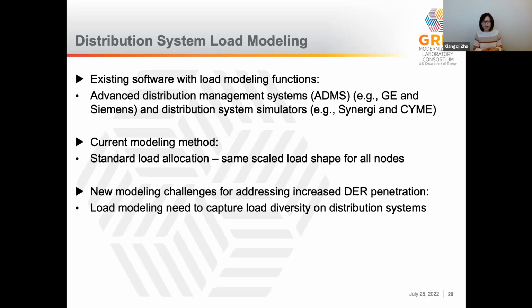One group is the advanced distribution management system, or ADMS, and the other is distribution system simulators like OpenDSS or CYME. Load modeling right now is a basic module in those software packages, often serving as a function called load allocation. When we perform time series analysis, each node in the system is populated with a load shape, which is the same as that of the system substation. The only difference between the load profiles of the nodes is the magnitude, decided by the customer transformer capacity on each node.